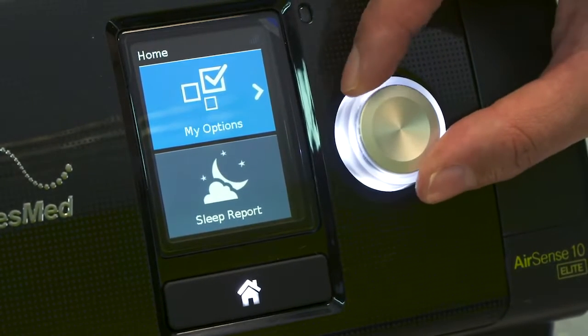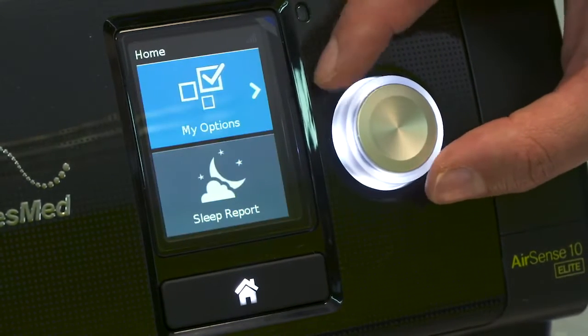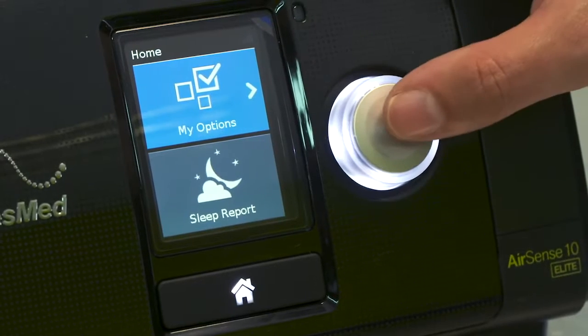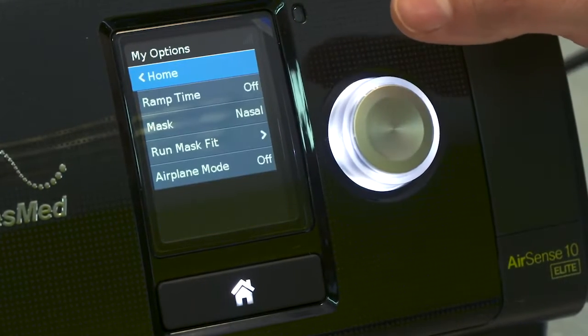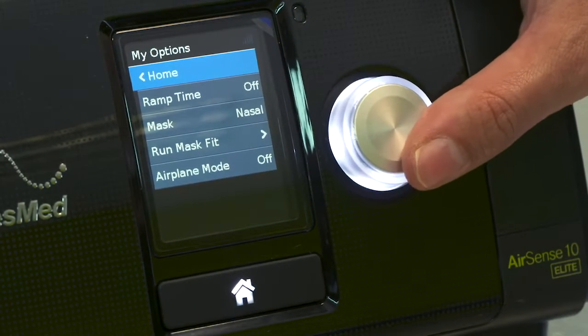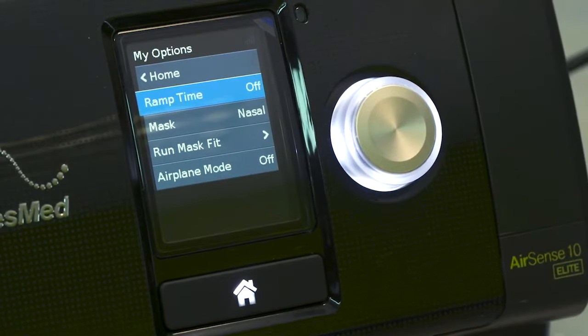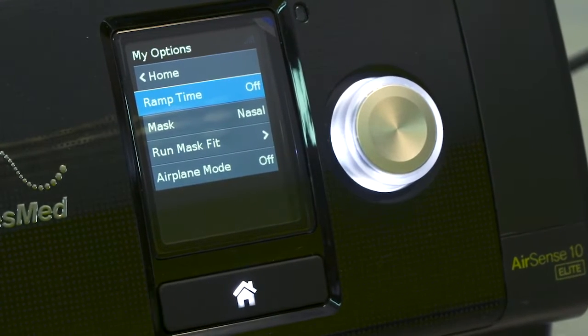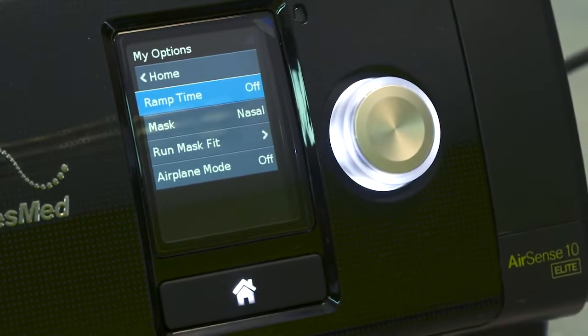When you turn the dial, whatever you highlight in blue, you can then select. So in My Options, we'll push the dial down to select that. The first option is the ramp time. The machine gives you a period of time where it starts at the lower pressure and will gradually build up to give you a period of time so you're comfortable and you're able to fall asleep before it reaches the higher pressure. There are two ways of setting this.